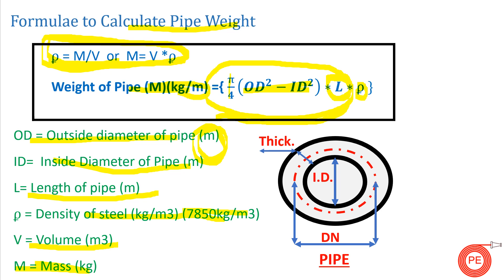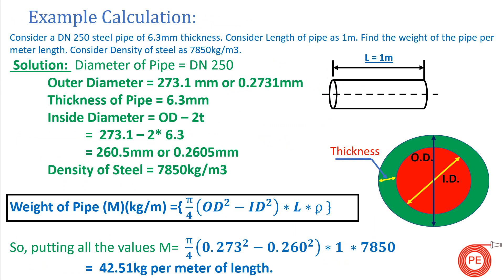Let's see how to calculate the weight of a pipe with the help of an example. Consider a DN 250 steel pipe of thickness 6.3 mm and length 1 meter. We need to calculate the weight per meter length. Density of steel is given as 7850 kg/m³. For a DN 250 pipe, the outside diameter is 273.1 mm. The outside diameter is fixed for a given DN; only the thickness and inside diameter vary.